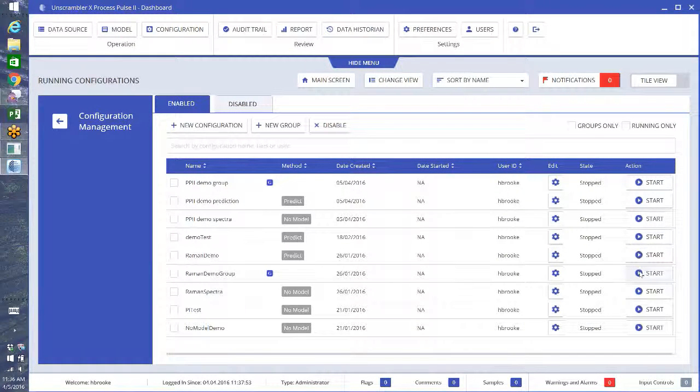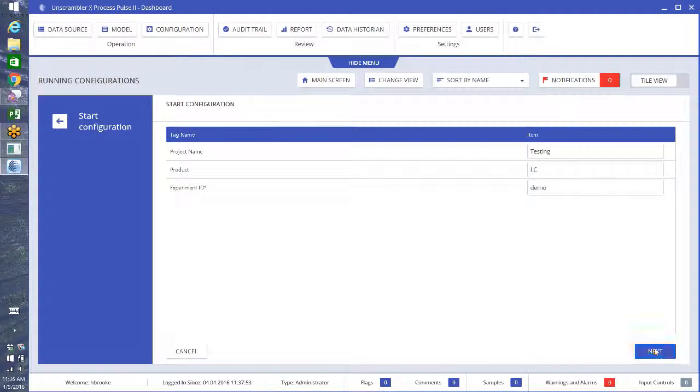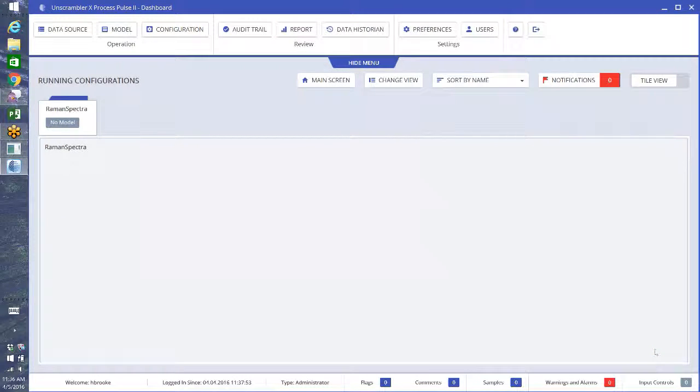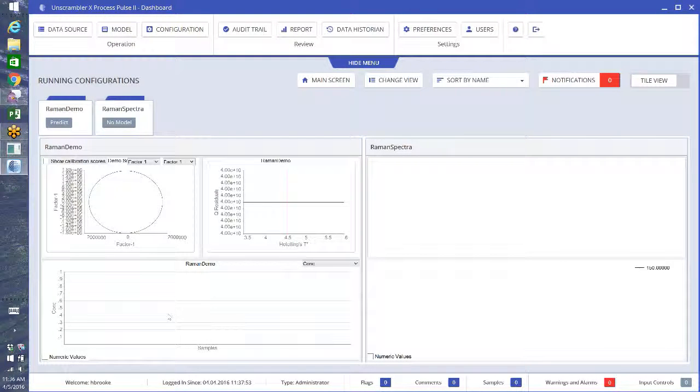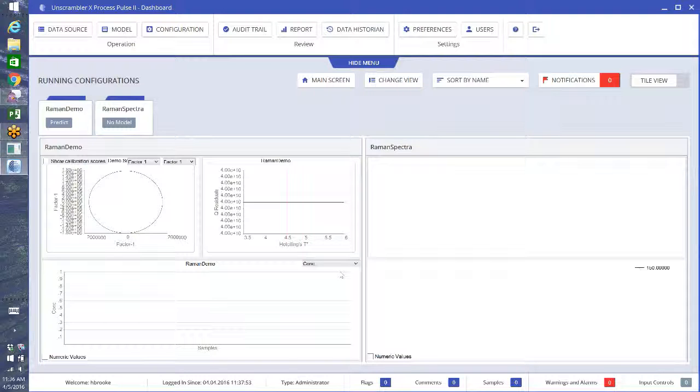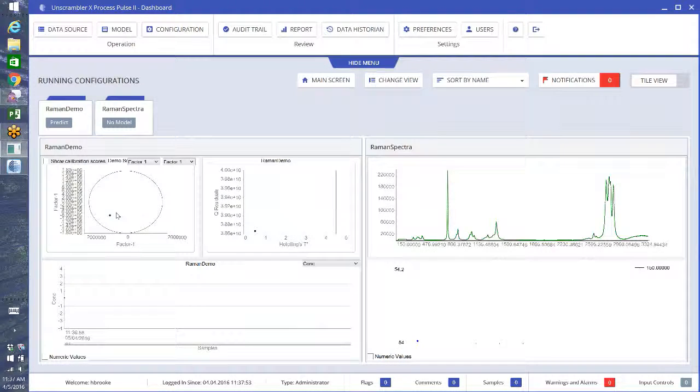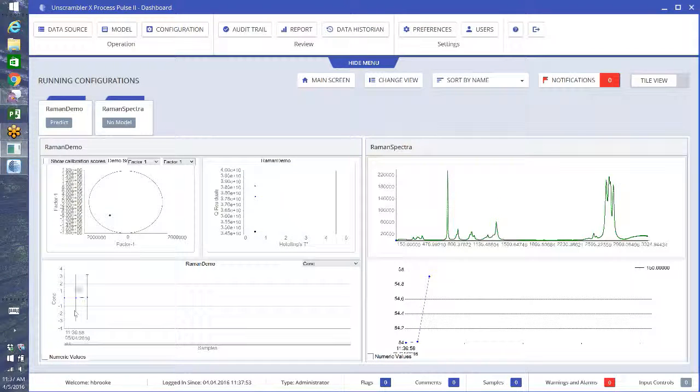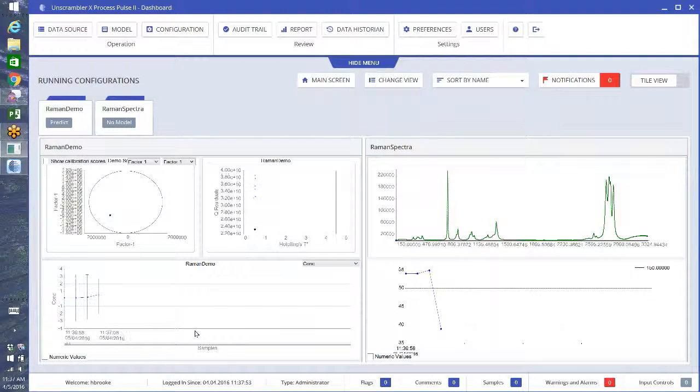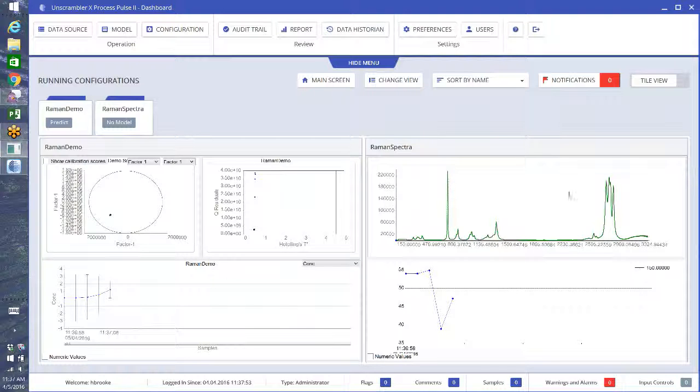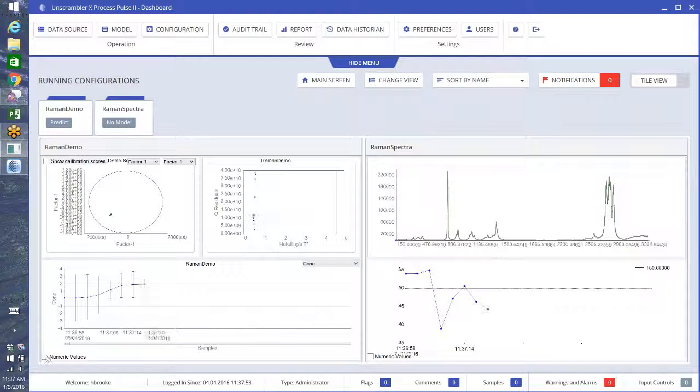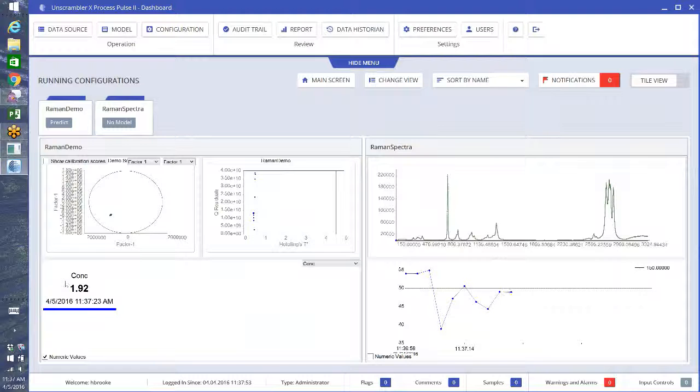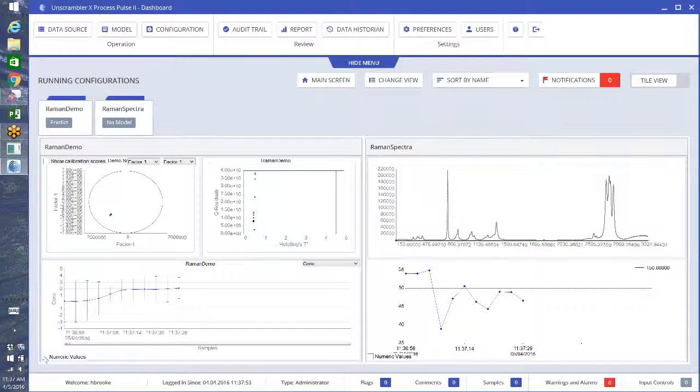You run this one since I know that one works. There we go, and now we have our things that show up very nicely. Now nothing's happening and that's because I don't have a spectrometer running, so I'm going to run that and you'll see the data points show up and you can follow them. You've got your prediction with your error bars. That's how confident we are in that particular prediction. And here on the Raman spectra, you can see what the raw spectra looks like as it goes along. We can also just change this to numeric values so it just tells you what the concentration is as it's coming out, and that will run until you stop it.